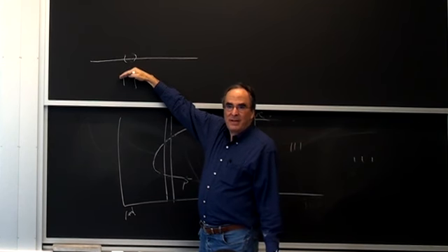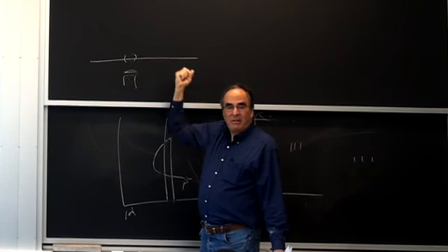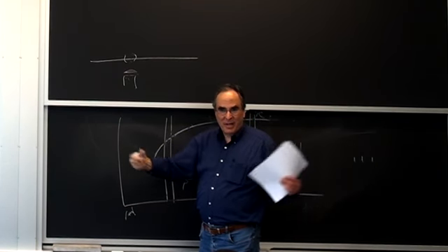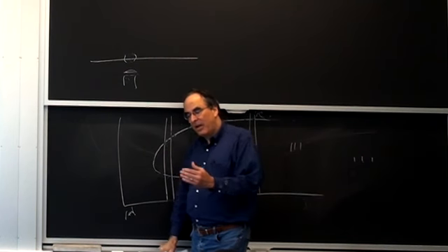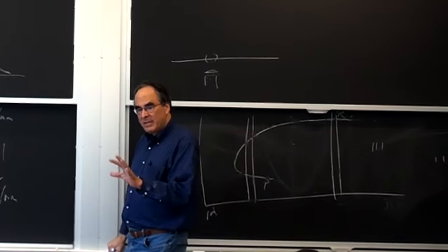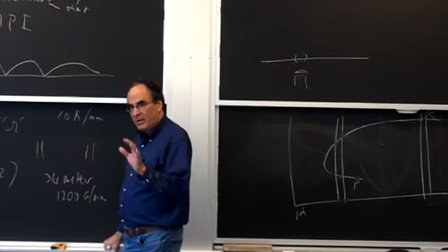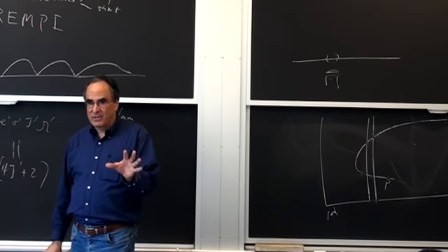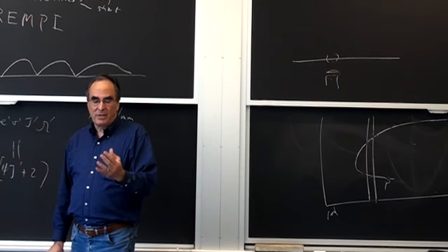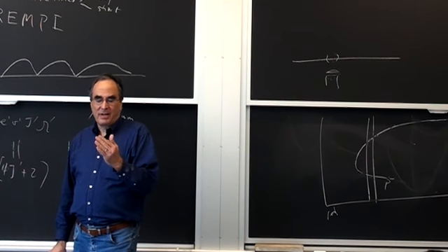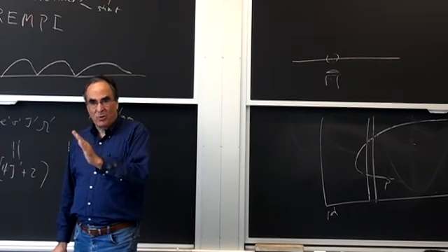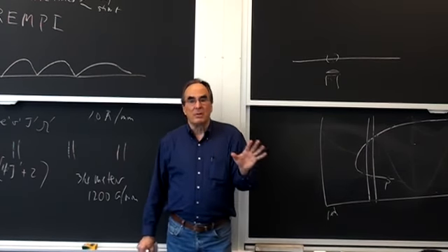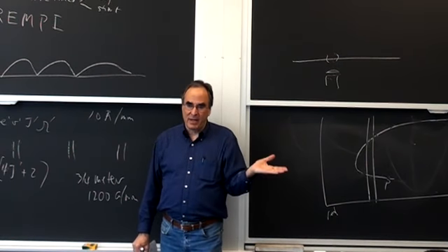That costs you a factor of 10. You don't need a filter with the monochromator because it's a super filter. And so that takes you down to, now then there's the issue of how efficient is the grating? Is the grating 100% efficient? Well, holographic gratings are very, very high efficiency. But then there's the issue of whether it is a blaze grating and which order you work. So roughly, you use a monochromator, you're losing a factor of 10, 100.